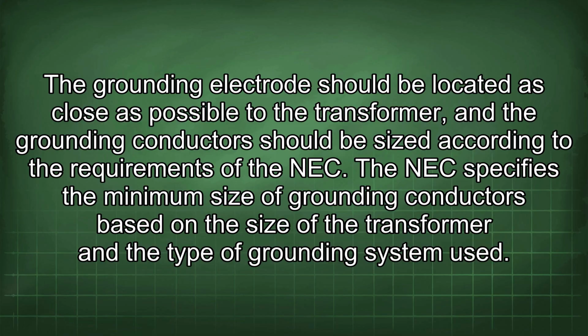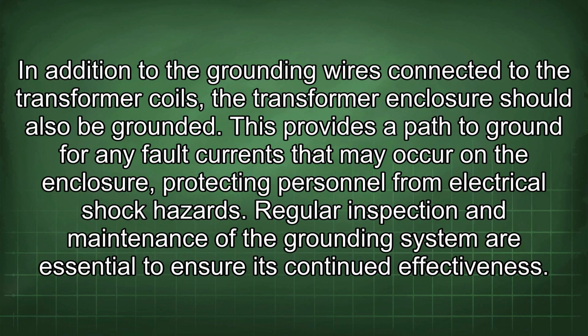The grounding electrode should be located as close as possible to the transformer, and the grounding conductors should be sized according to the requirements of the NEC. The NEC specifies the minimum size of grounding conductors based on the size of the transformer and the type of grounding system used. In addition to the grounding wires connected to the transformer coils, the transformer enclosure should also be grounded. This provides a path to ground for any fault currents that may occur on the enclosure, protecting personnel from electrical shock hazards.